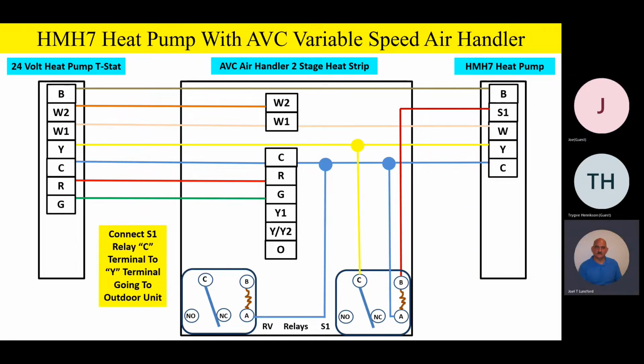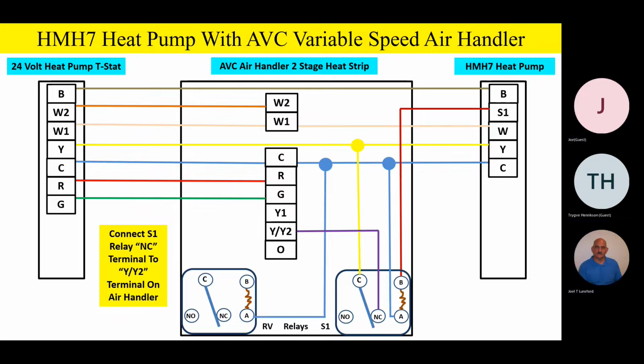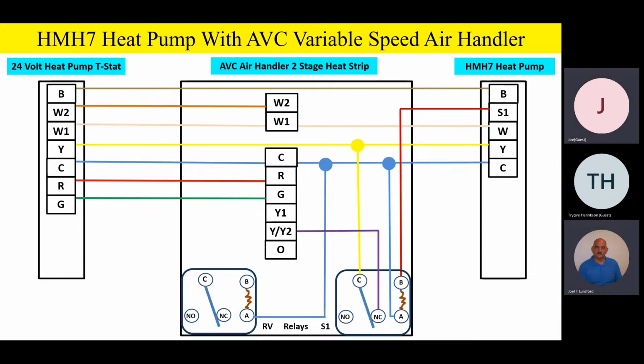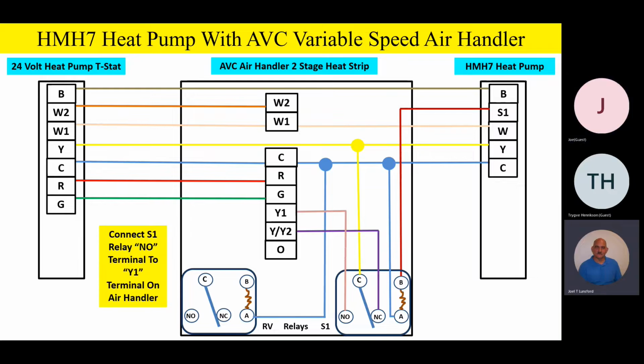On the S1 relay, we're going to take the Y signal to the outdoor unit, from the thermostat to the outdoor unit. We're going to tie it onto the common switching terminals on the S1 relay. The normally closed contact on the S1 relay is going to go over to Y/Y2, very much like we had before for our high-speed airflow in the cooling mode of operation, that Y/Y2. And then the normally open on the S1 relay is going to go to Y1. So this is very similar to what we've had before with just a single relay.